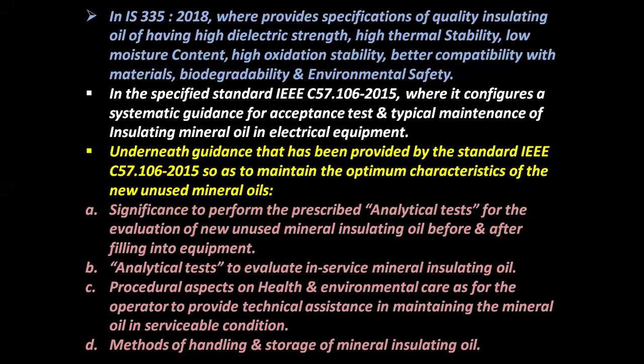The standard IEEE C57.106 2015 configures systematic guidance for acceptance tests and typical maintenance of insulating mineral oil in electrical equipment. Underneath is the guidance provided by the standard IEEE C57.106 2015 so as to maintain the optimum characteristics of new unused mineral oils.